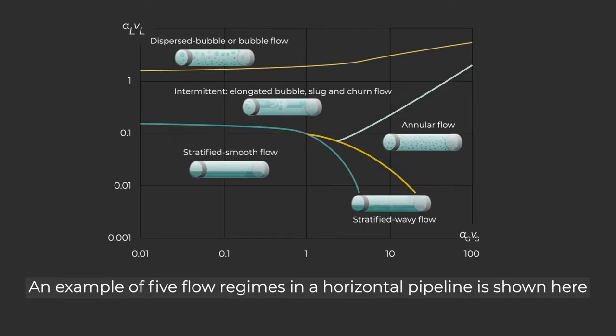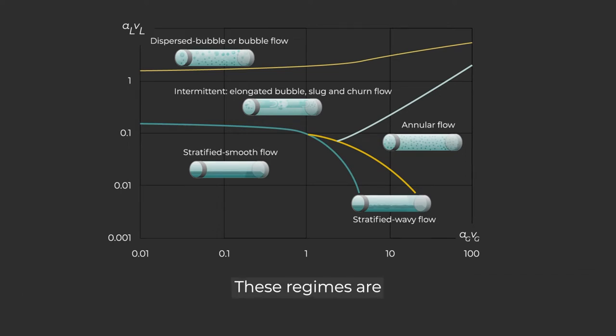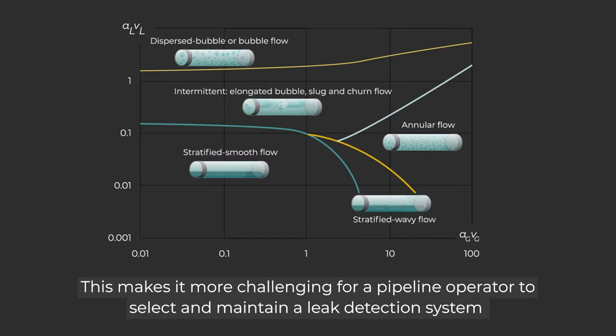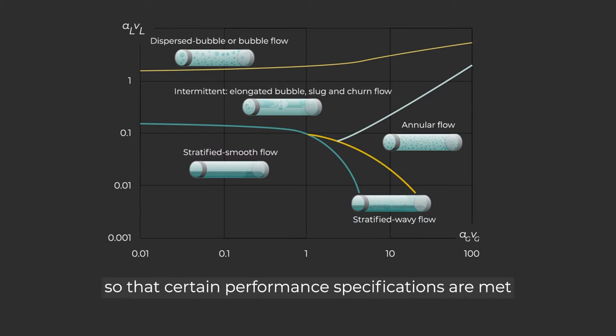An example of five flow regimes in a horizontal pipeline is shown here. These regimes are dispersed bubble or bubble flow, intermittent elongated bubble, slug and churn flow, stratified smooth and wavy flow, and annular flow. It is possible for a pipeline to be running under different flow regimes at different times, making it more challenging to maintain a leak detection system.